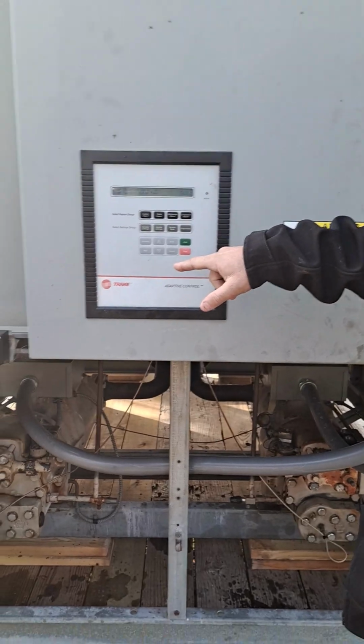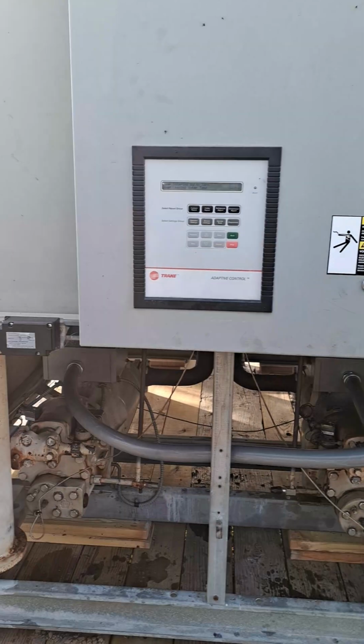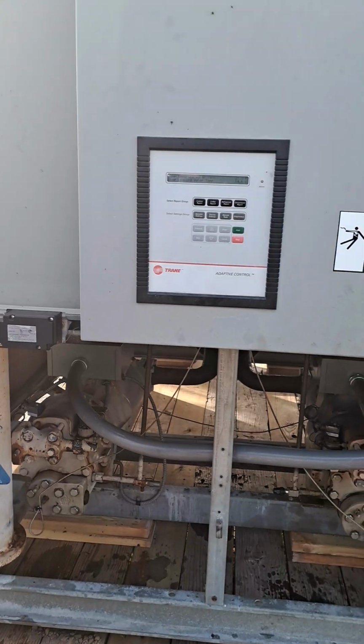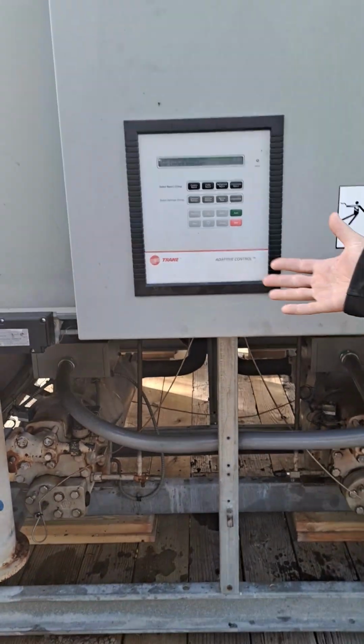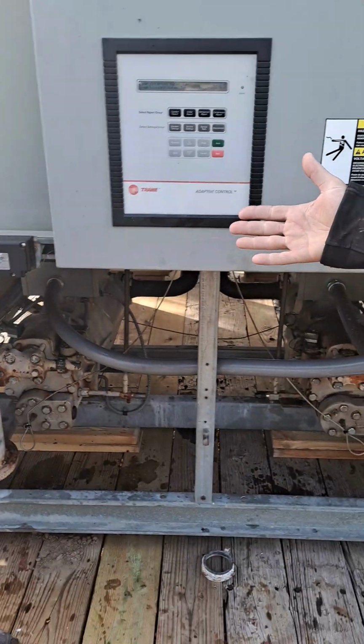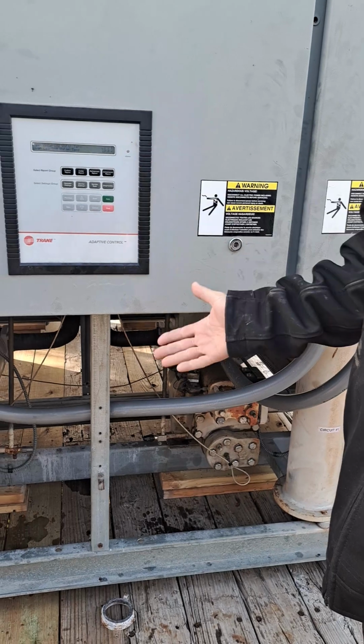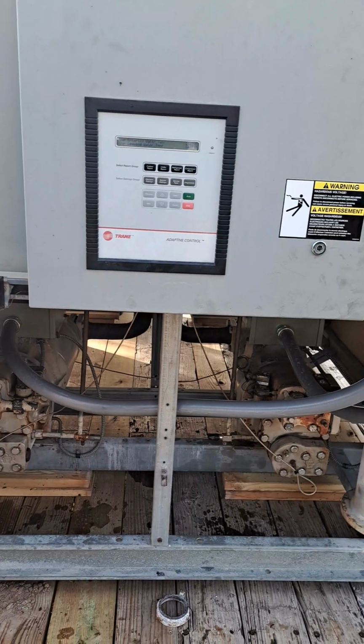Stop button, and it'll go through a shutdown process and shut off. So it won't just kick off. It'll go through a process as it shuts down. Yeah, the compressors have to unload. You don't want them starting loaded up. That's really high amp draw. So these things are designed to unload 100%, and then they shut off. So it takes a few minutes for it to shut down.